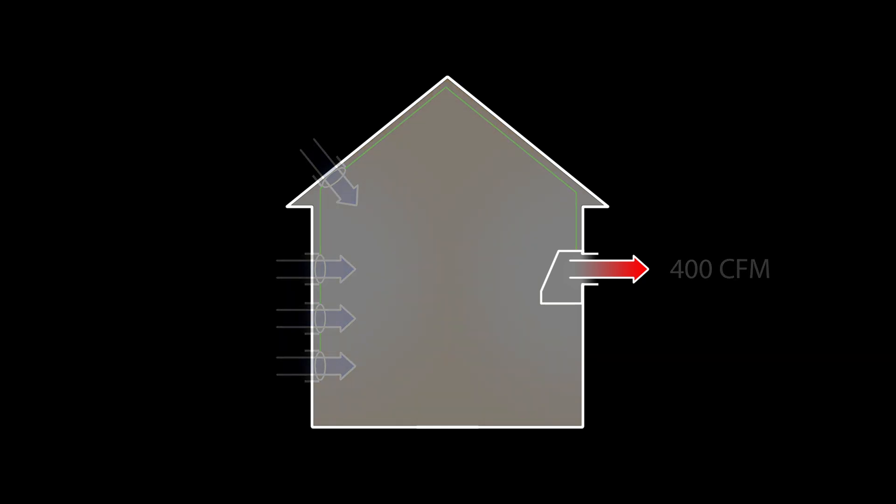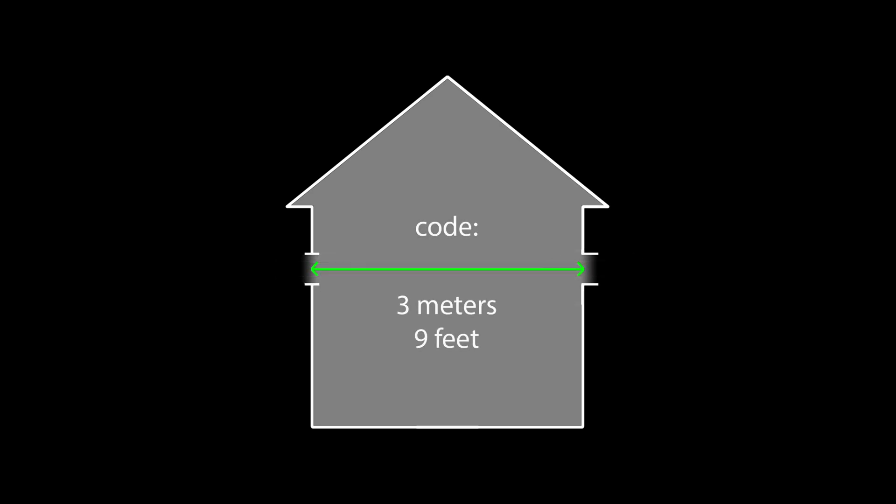A couple of other notes is that the location of this passive intake does matter. The closer it is, the better, and the minimum distance between the intake and the exhaust needs to be at least three meters apart.